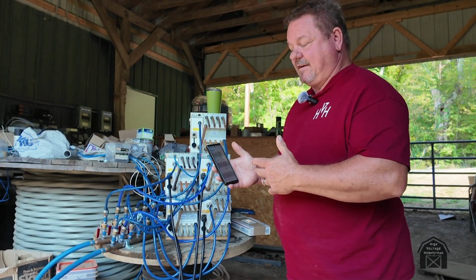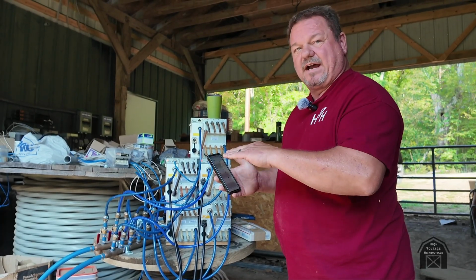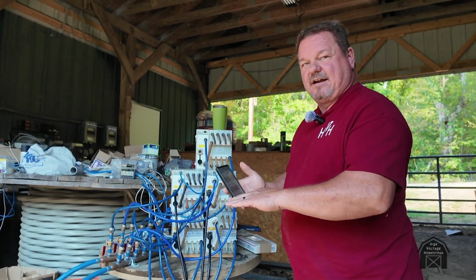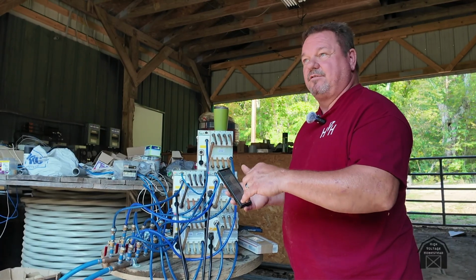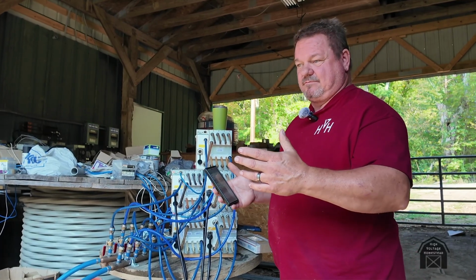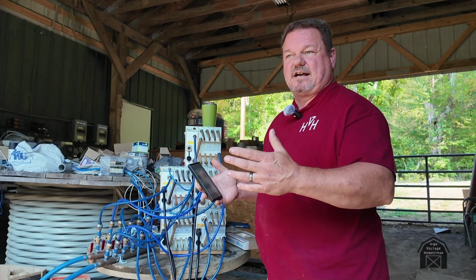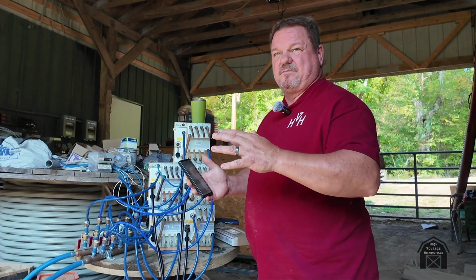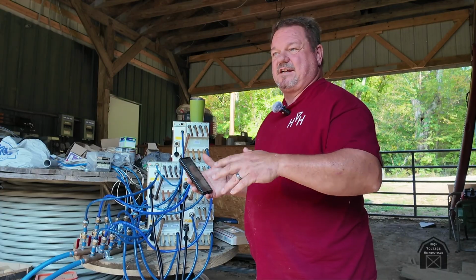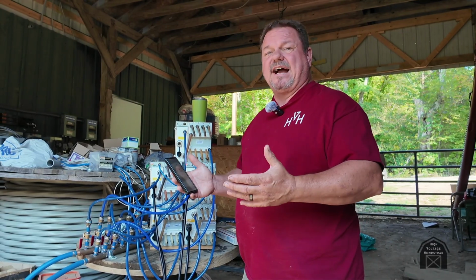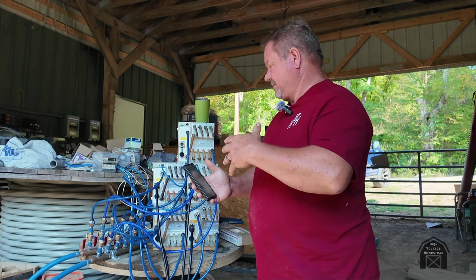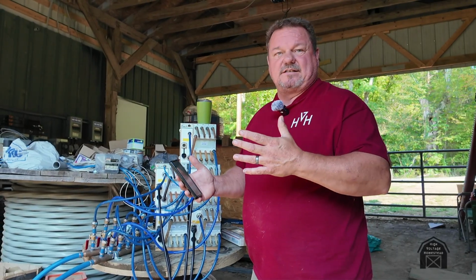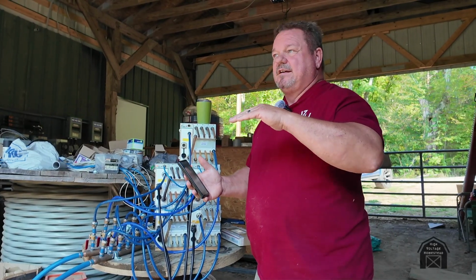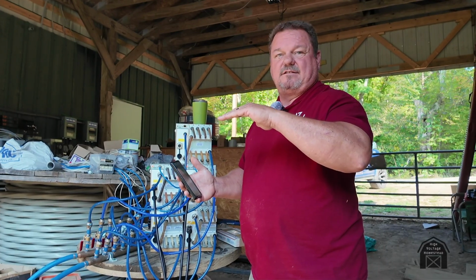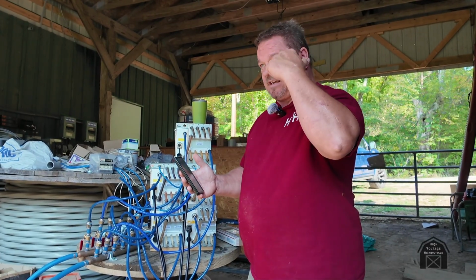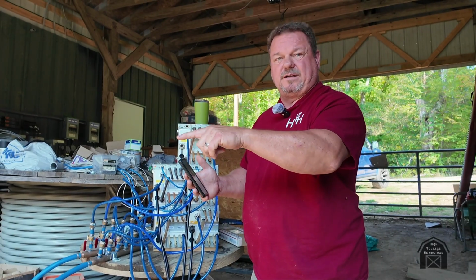Then at the end of the day, when I'm watching my state of charge on my batteries, and as it comes down, Solar Assistant will tell you this is depleting you at 2% an hour, 10% an hour. On a house that really doesn't matter because your loads constantly change, so it fluctuates. But for mining it's actually pretty good because the number of miners running doesn't change, so if it says you're at a 10% an hour depletion rate, that's going to be pretty steady, and you can calculate in your mind about how much more you're going to be able to run.